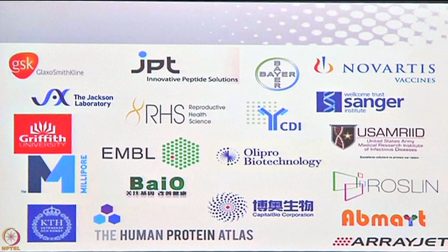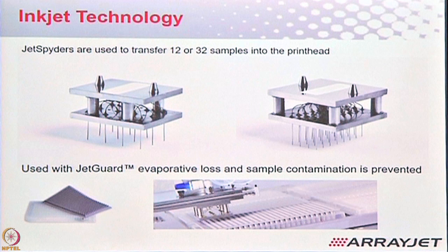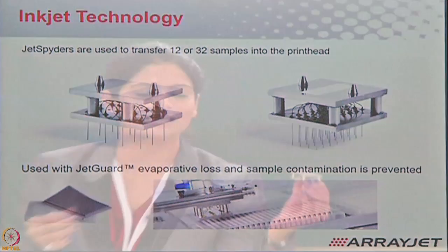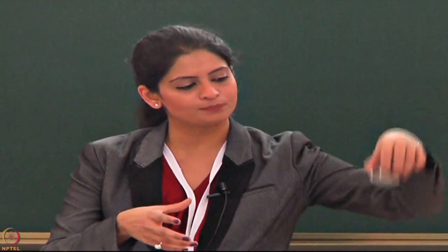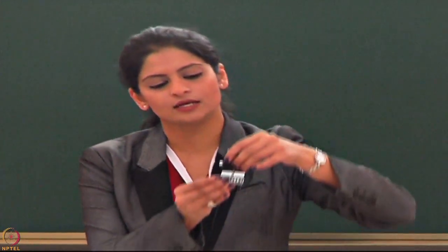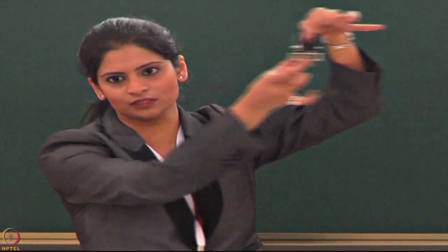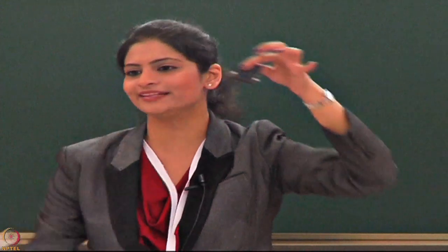The technology uses piezoelectric printing at 0.2 meters per second. This is a liquid sample handler — the Jet Spider — which can simultaneously aspirate sets of 12 or 32 samples. Depending on how many samples you have in a 384-well source plate, it aspirates the sample upwards and attaches to the print head. The biggest difference from most technologies is that we don't need pins — most technologies use pins to take and deposit samples, but pins are brittle, they break, they get clogged, and require a lot of maintenance.